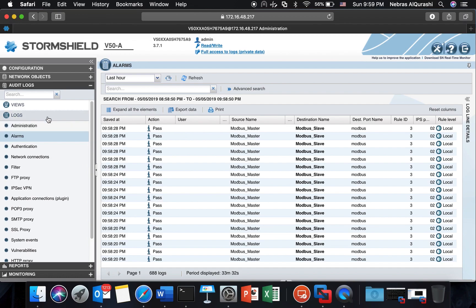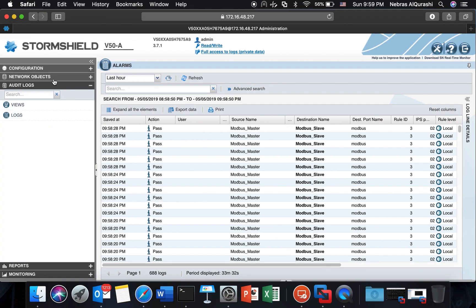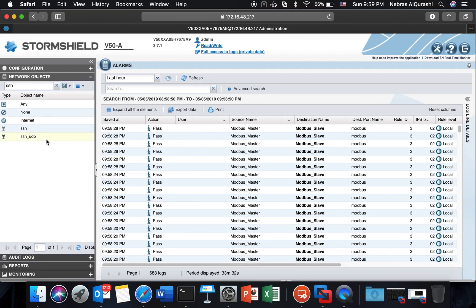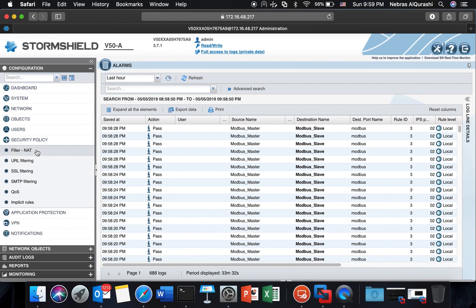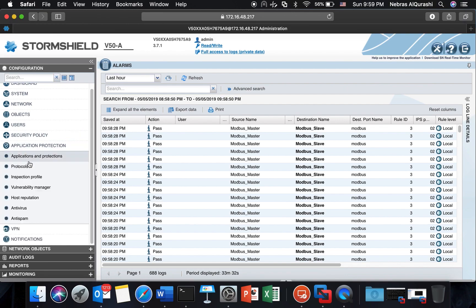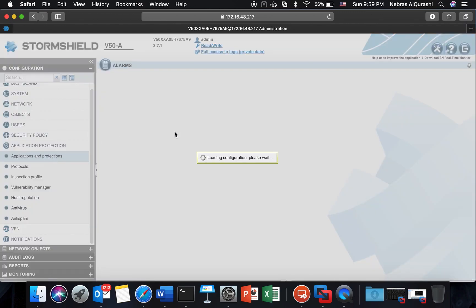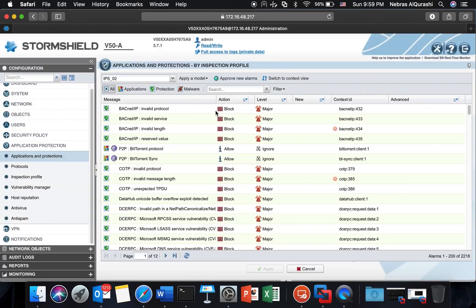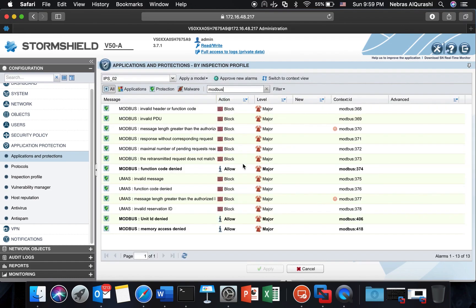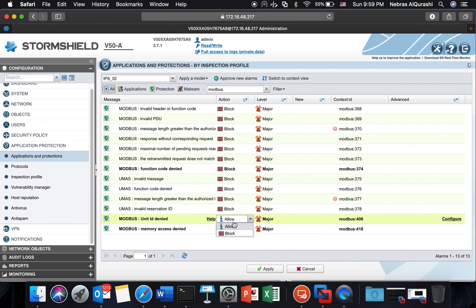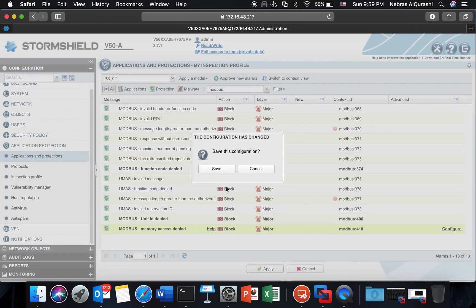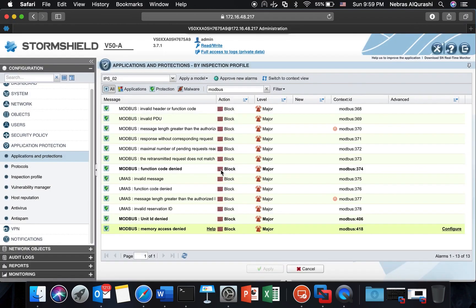Let me also set the alarms to block just to make sure that I have the good configuration. I'm going to application protection applications and protections to the one that I have set on IPS 02, the Modbus. I will change set them to block in case I have a wrong function code, in case I have a wrong unit ID, and in case if I have a wrong address management. So I'm blocking them all.